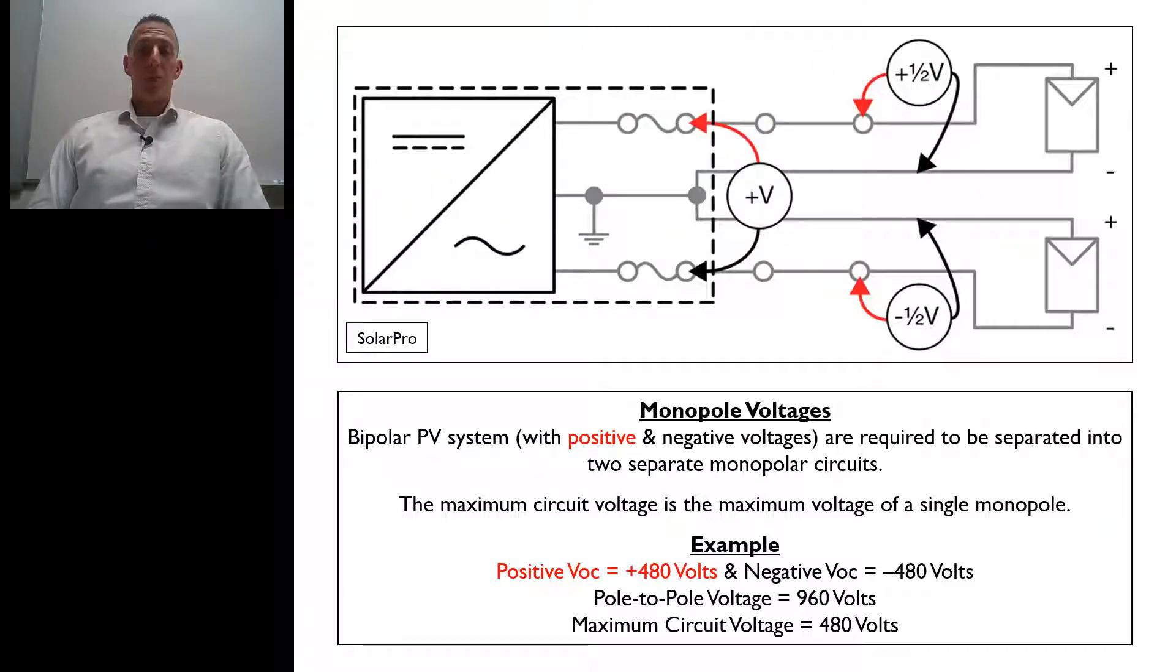To provide a little more information and get a little bit more in depth about how we're going to look at these voltages and the requirements of 690.7c of the 2017 National Electrical Code, I want to illustrate and show you what those monopole and the total bipolar voltage would look like. Bipolar PV systems with positive and negative voltages are required to be separated into two separate monopole or monopolar circuits.